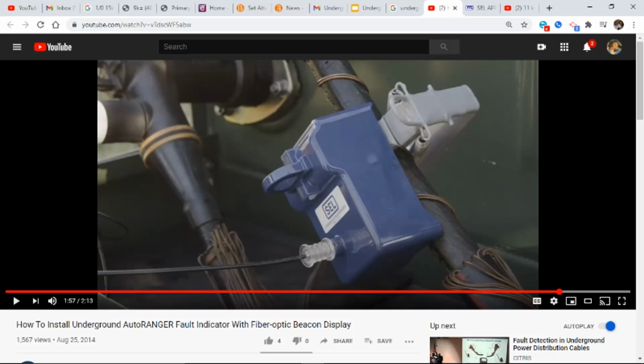Okay, I want you to pay attention closely. Do you see what's wrapped around the primary conductor here and going up to the transformer? What are those two wires right there? Copper. Is it ground? Is it neutral? Ground. Yeah, it's a grounded neutral, and he's got the fault indicator over the top of it. Now he's only taking 2 strands, and you'll do that to go up to the elbow itself. This one on the left-hand side, there's an attachment point right here at the bottom to be able to make sure you've got the outside of the elbow grounded, which is general practice. That is normal practice.